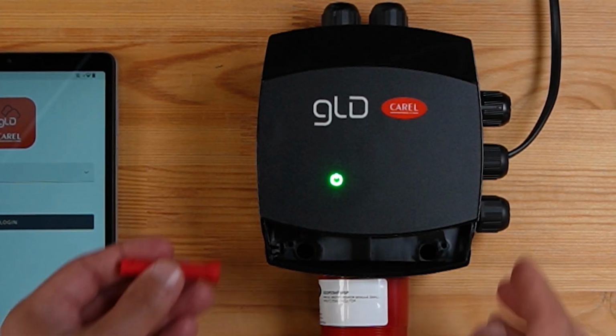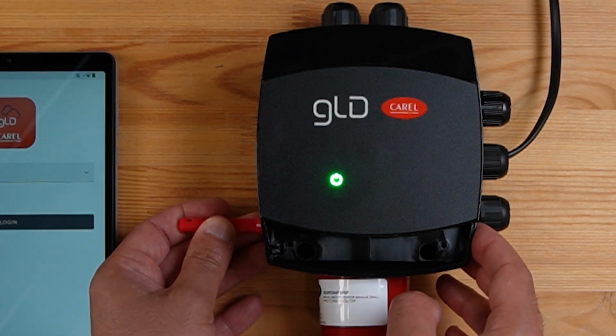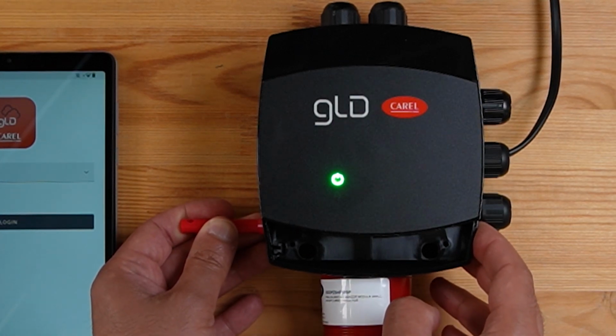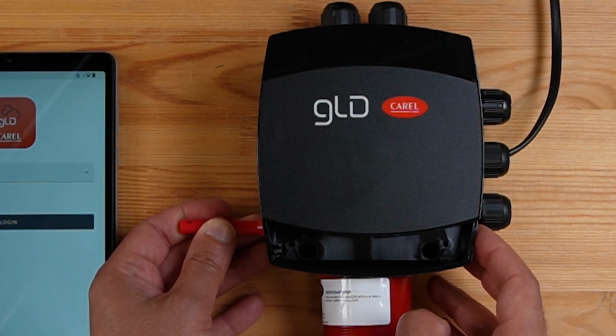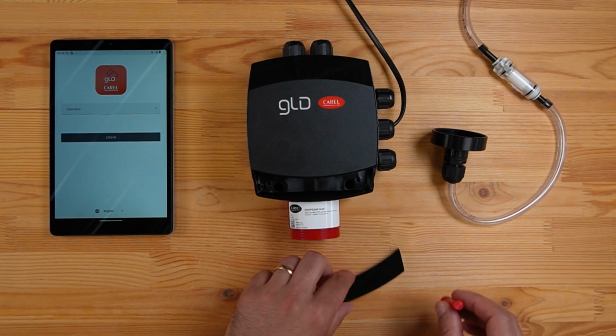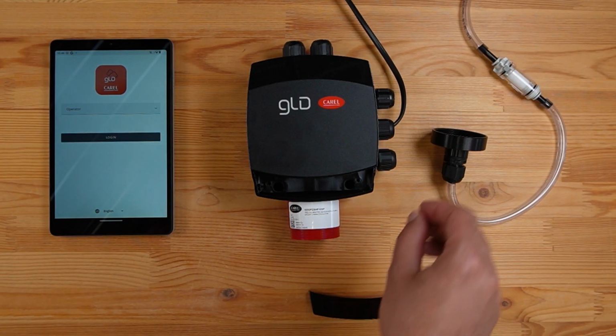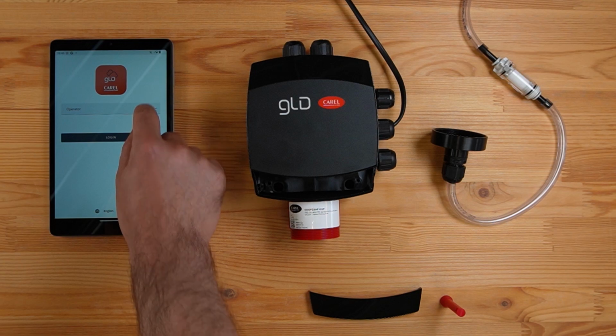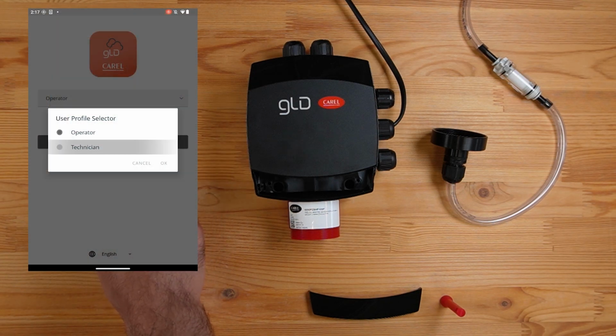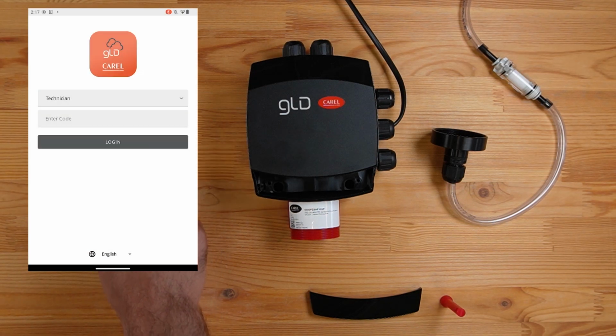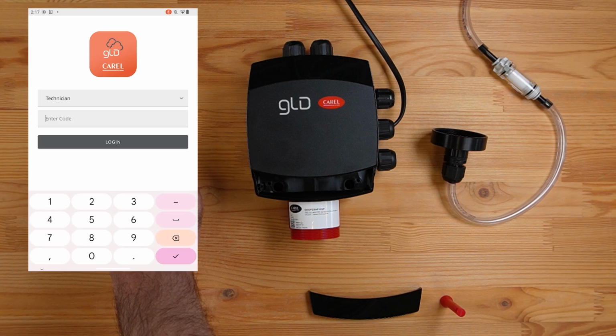Hold the magnetic wand on the marked spot on the left side of the unit for 5 seconds, until the green LED light starts flashing. This means the unit is now in service mode and will not trigger any warnings or alarms via relays or Modbus. Connect the app by choosing Technician. Then enter the passcode to access the unit.